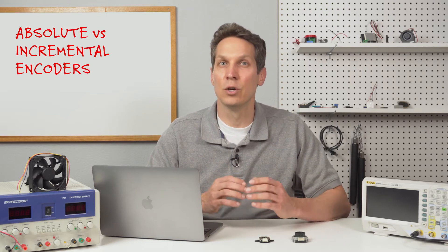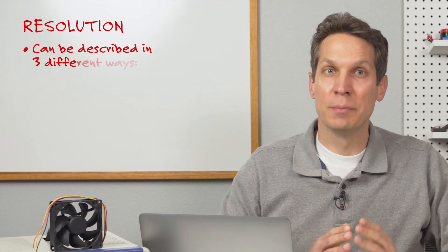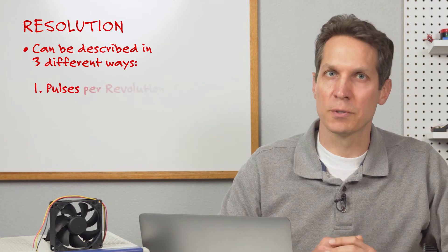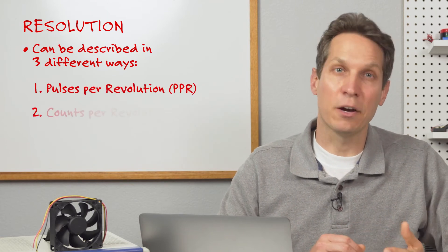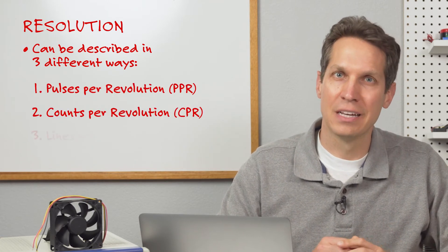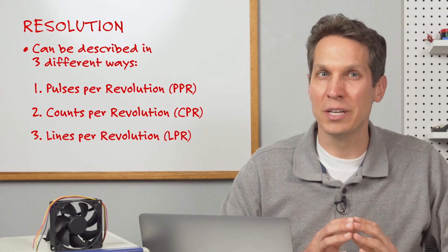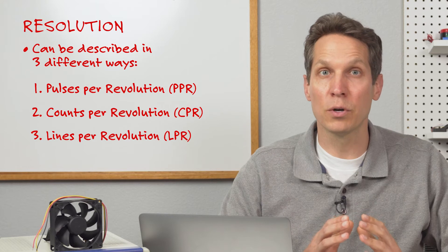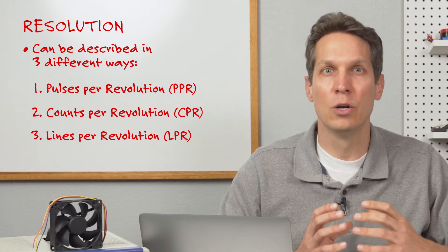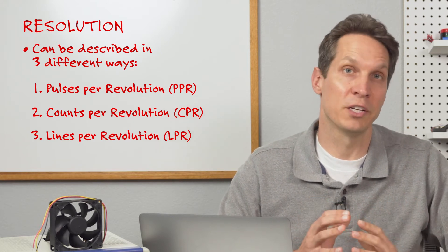it is necessary to know the encoder's resolution. Resolution can be described in three different ways: pulses per revolution or PPR, counts per revolution or CPR, and lines per revolution or LPR. As resolution is notated differently across the industry, it's important to get the numbers into the same format when comparing products from different encoder manufacturers.